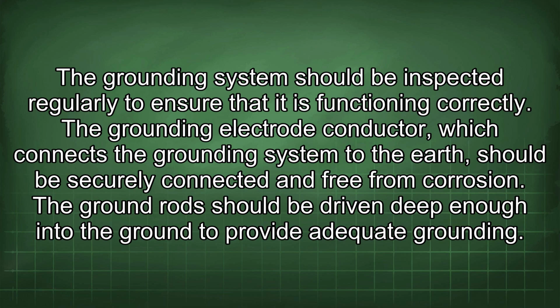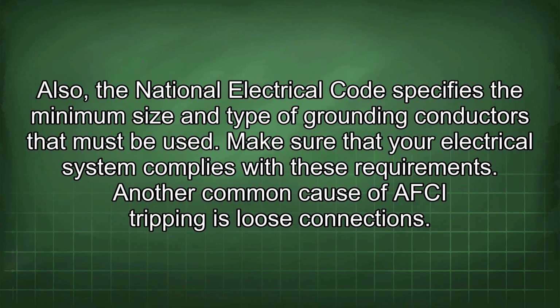The grounding electrode conductor, which connects the grounding system to the earth, should be securely connected and free from corrosion. The ground rods should be driven deep enough into the ground to provide adequate grounding. Also, the National Electrical Code specifies the minimum size and type of grounding conductors that must be used. Make sure that your electrical system complies with these requirements.